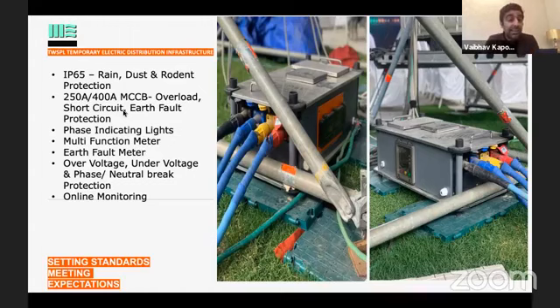Again, MCCBs are there, so overload, short circuit, and earth fault protection are there. Phase indicating lights: on the right side picture, at the bottom, there are 3 lights, which tell me that my genset is on and my 3 phases of electricity are absolutely fine. Then we have the multi-function meter. There is a meter on top which shows me my parameters of electricity: voltage, frequency, load, whatever you want to know. Rather than having a multimeter, everything is shown on site, even to a layman who doesn't understand, but understands that there should be 50 frequency and all that.